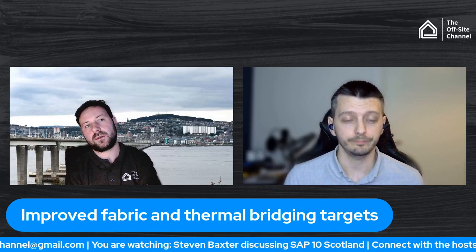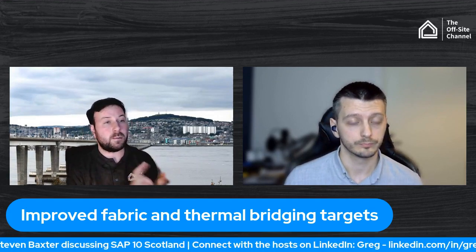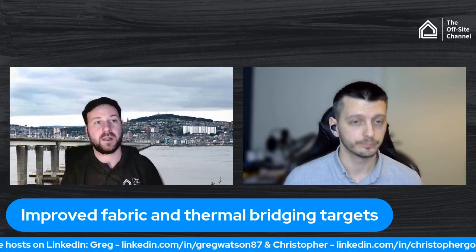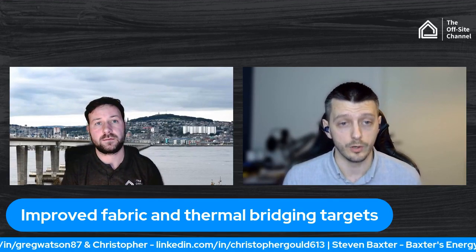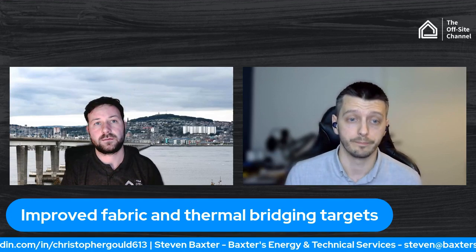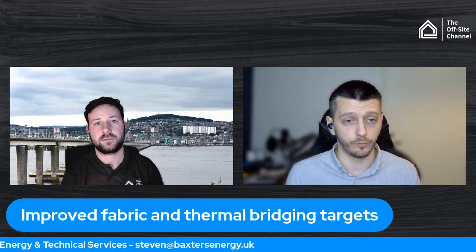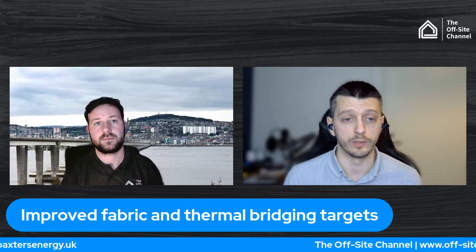And so regarding the U value of, say, a standard timber frame wall, masonry outer, cavity, timber kit, what do we have to do to meet the regulation? Well, to meet the regulations for walls, for example, the new area weighted average U value is 0.17. So you can't have the total U value across the building for your walls averaged out to be more than 0.17.